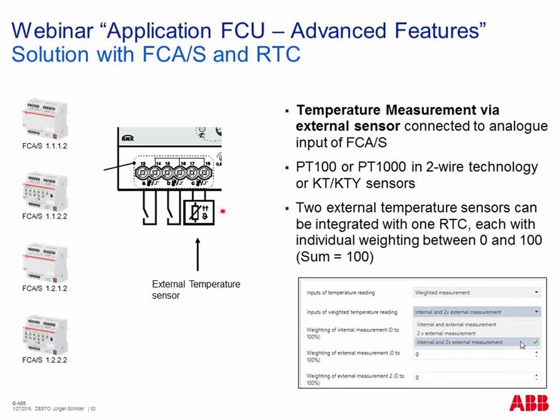Additionally, we can use an input channel as an analog input for external temperature measurement. You can connect directly a PT100 or PT1000 temperature sensor, install it in your room, and send the measured value to the room temperature controller. This allows adding this additional measurement to the total room temperature evaluation. It's possible to add up to two external measurements to the internal measurement — where internal measurement is the sensor inside the room temperature controller. Weighting is also possible here, making you very flexible to measure temperature in large rooms.